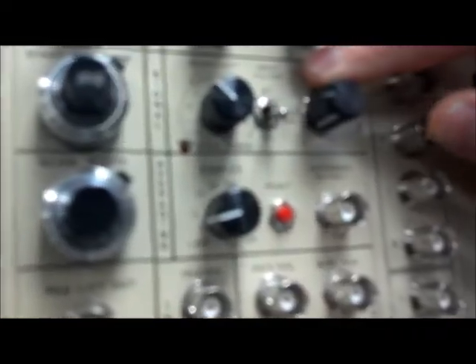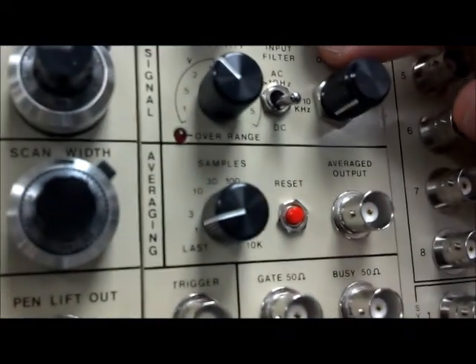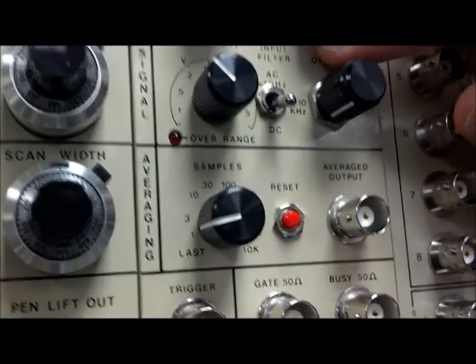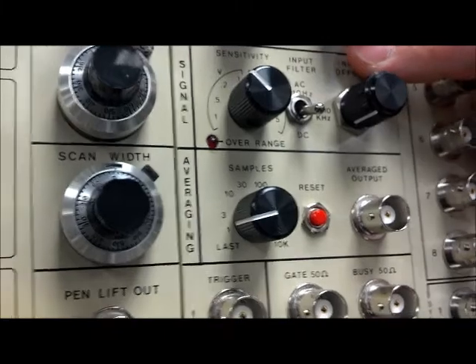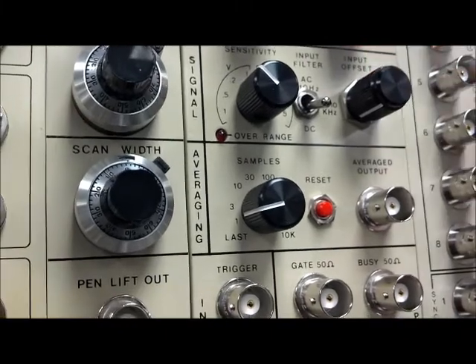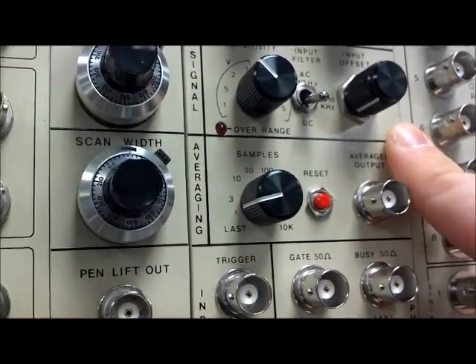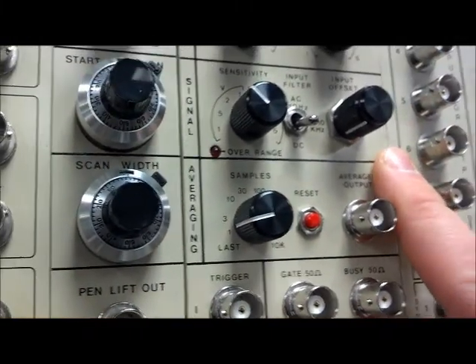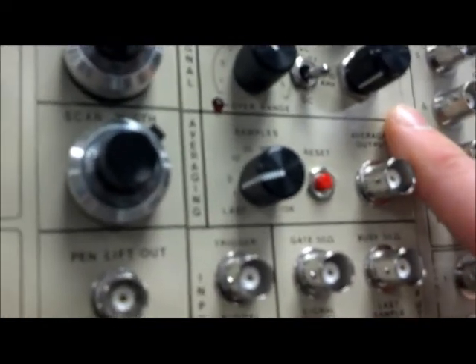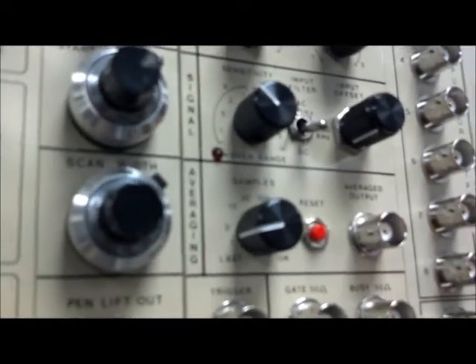Next is a switch that controls the input filter. This can be set to a number of different levels to reject unwanted noise coming from the signal that is being attempted to recover. The input offset allows the user to compensate for unwanted DC offsets that are included in the signal.